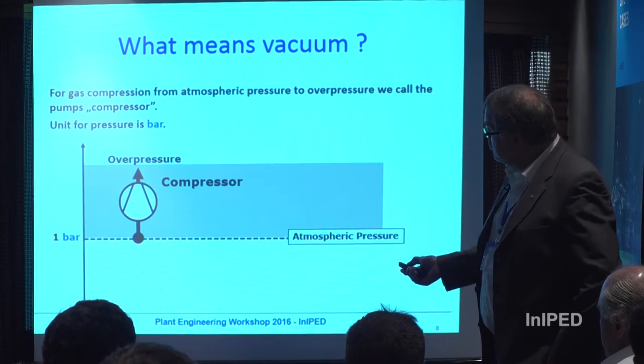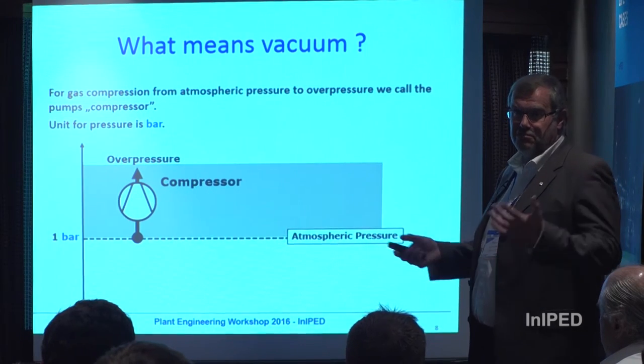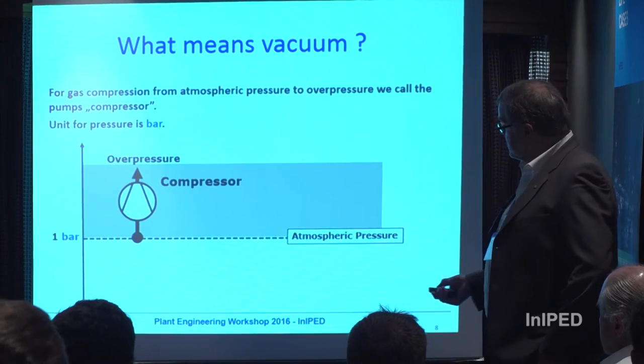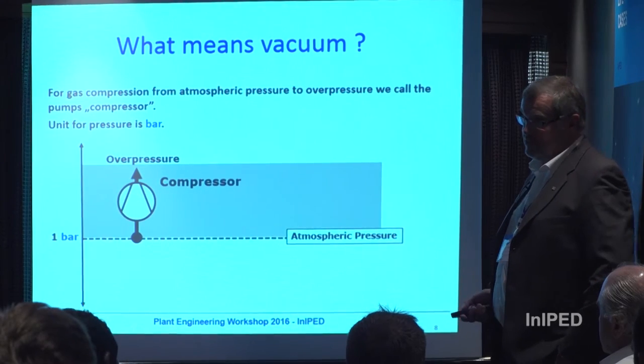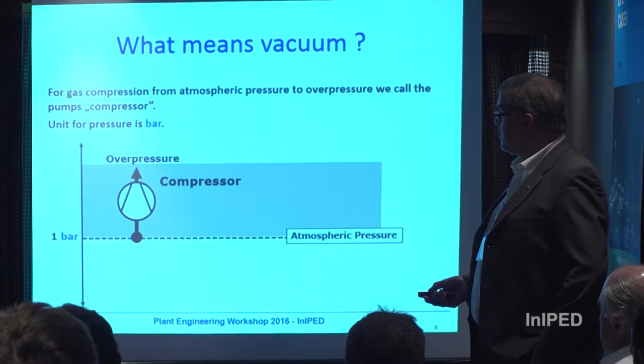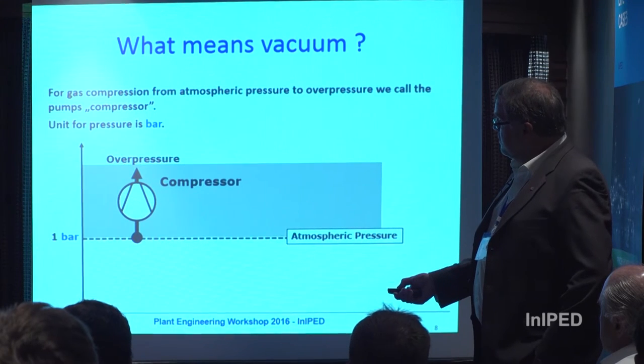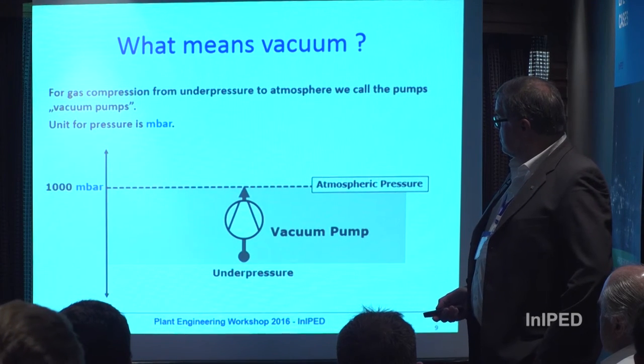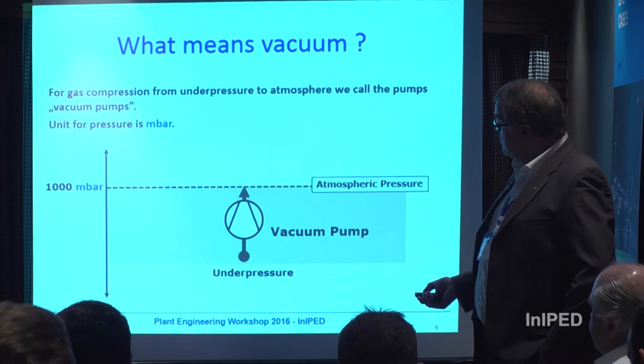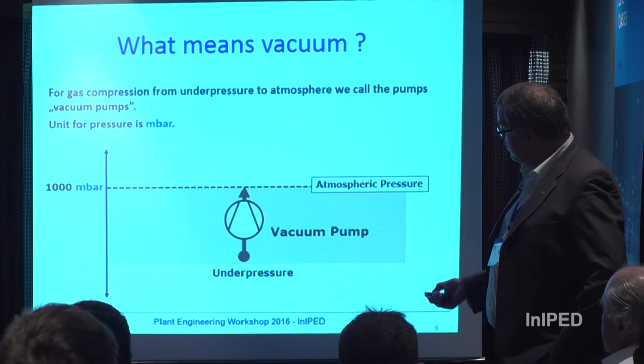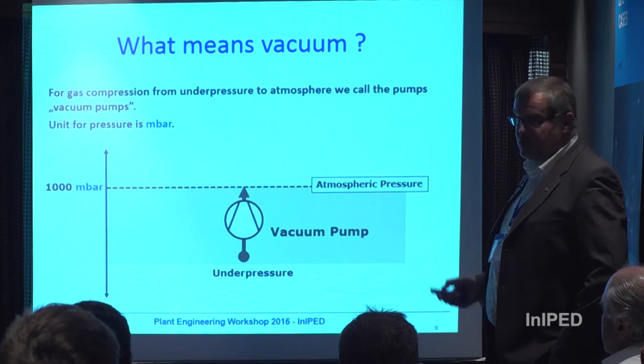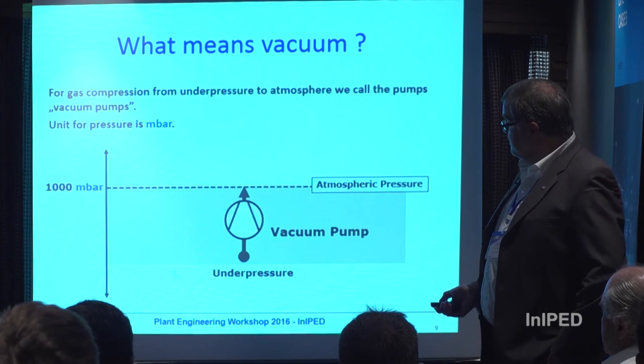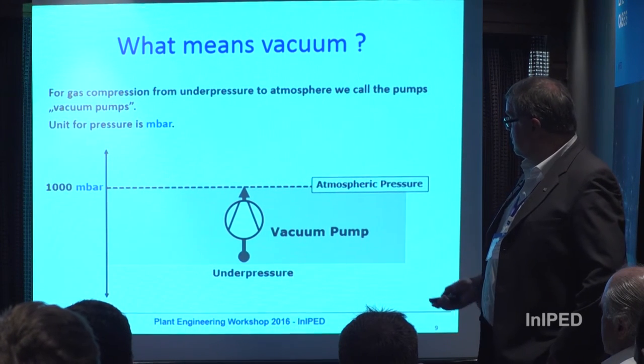When do we talk about a compressor and when about a vacuum pump? The machine looks very similar and is more or less the same. We talk about a compressor when, on the suction side, we are in the atmospheric pressure range — compressing gas from atmospheric pressure to overpressure. Typically we use bar as a unit. When we talk about vacuum, we mean a pump which handles pressure below atmospheric pressure and compresses it up to atmospheric pressure. In that case, we normally talk about millibar.